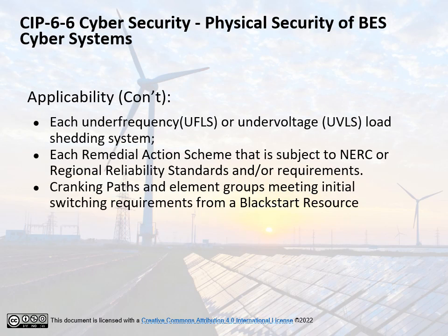CIP 6-6 Physical Security of BES Cyber Systems. Continued applicability: each under-frequency UFLS or under-voltage UVLS load-shedding system that is subject to NERC or regional reliability standards and/or requirements and performs automatically under a common control system without human operator initiation of 300 megawatts or more. Each remedial action scheme that is subject to NERC or regional reliability standards and/or requirements, cranking paths and element groups meeting initial switching requirements from a black start resource up to and including the first interconnection point of the starting station service of the next generation units to be started.